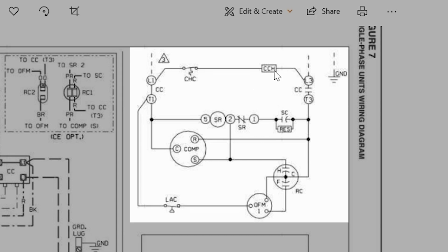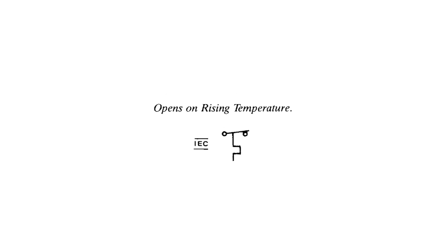But let's go through some of the basics. We'll start over here on the schematic diagram that shows it connected in between the two. So you're going to notice, for example, the first thing you see is CHC and CCH. Crankcase heater and our crankcase heater control. Our crankcase heater control is a single pole, single throw switch, meaning it's only open or closed, and it opens on rise.